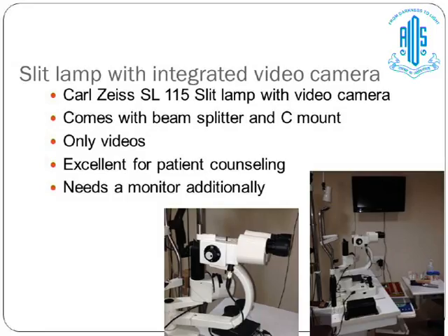Coming to the third pattern, which is the slit lamp with an integrated video camera. We use this system as well in one of our OPD rooms. This is an SL115 slit lamp from Zeiss with a video camera attached to it. The beauty of this system is that once you switch on the camera and the monitor, whatever the doctor is seeing in the patient's eye is projected on the screen, and the patient's relatives can see whatever is there. So it's again very useful for patient counseling, although you cannot record the images.